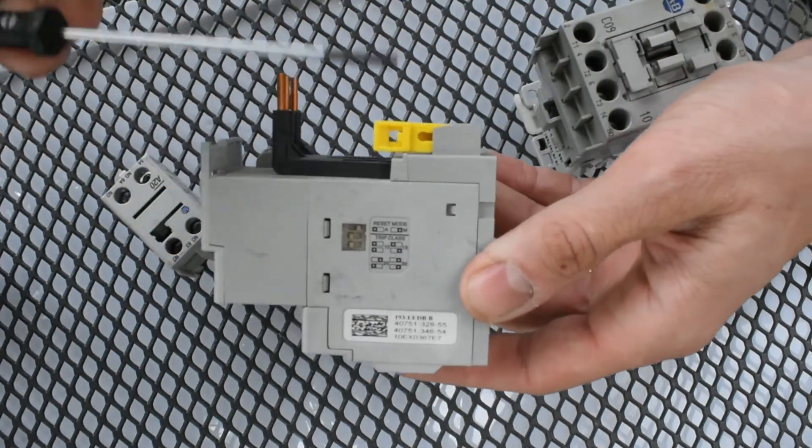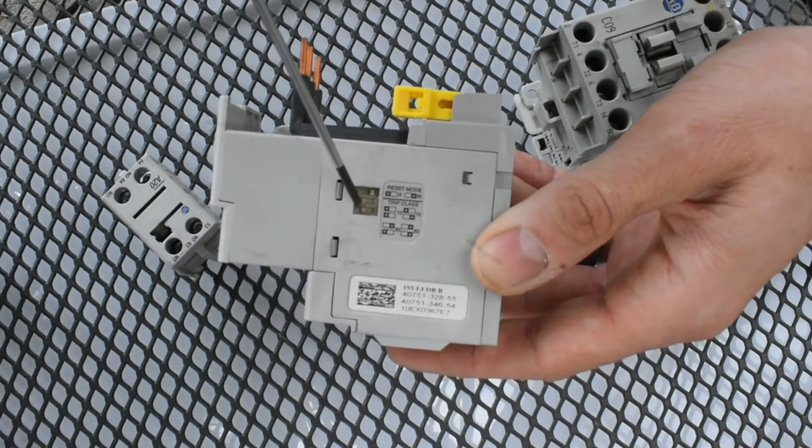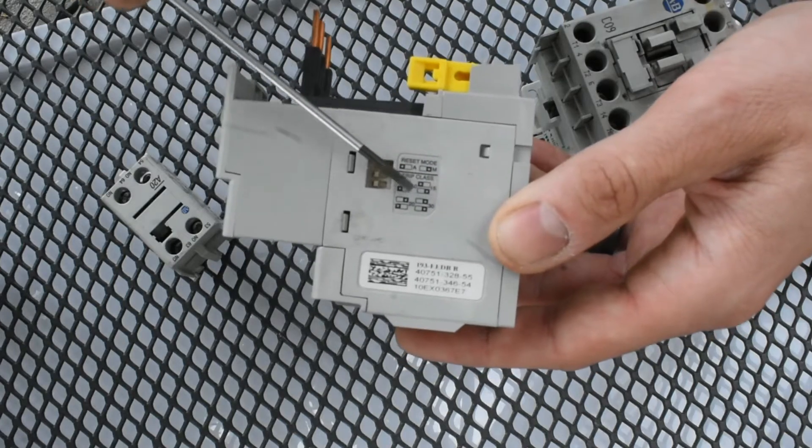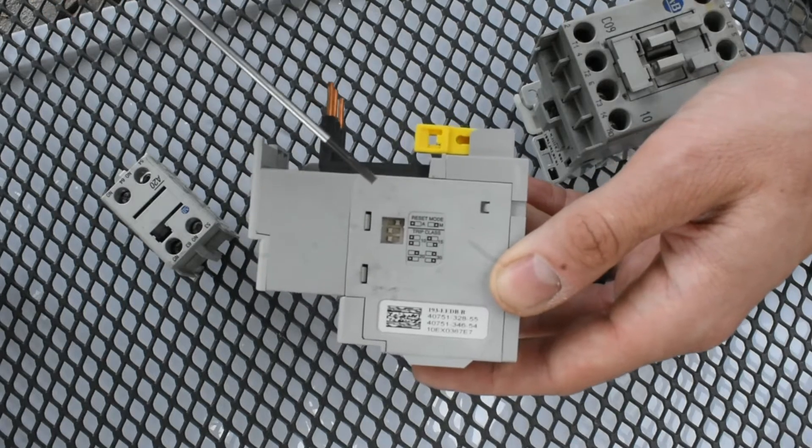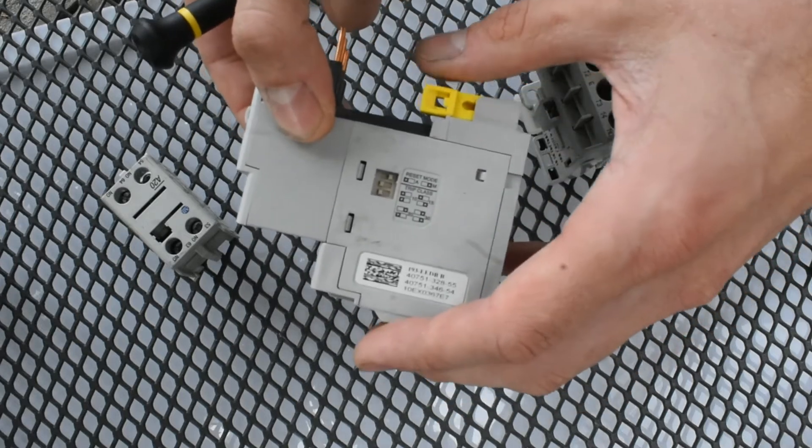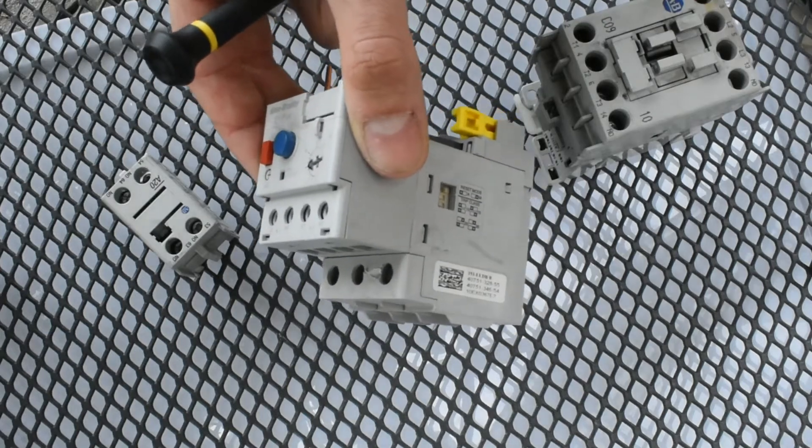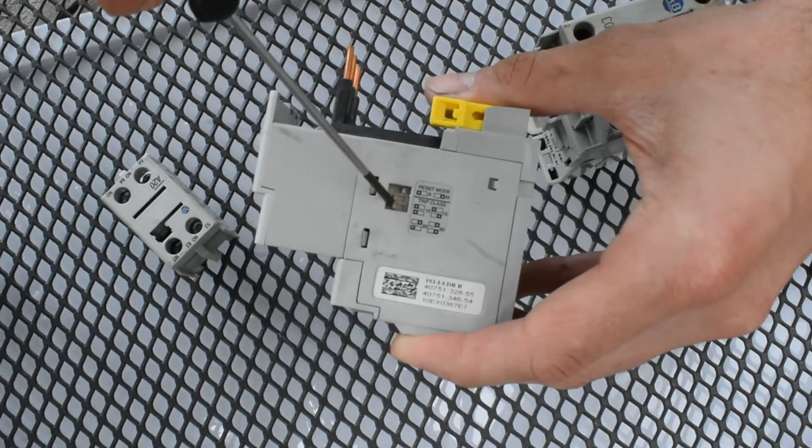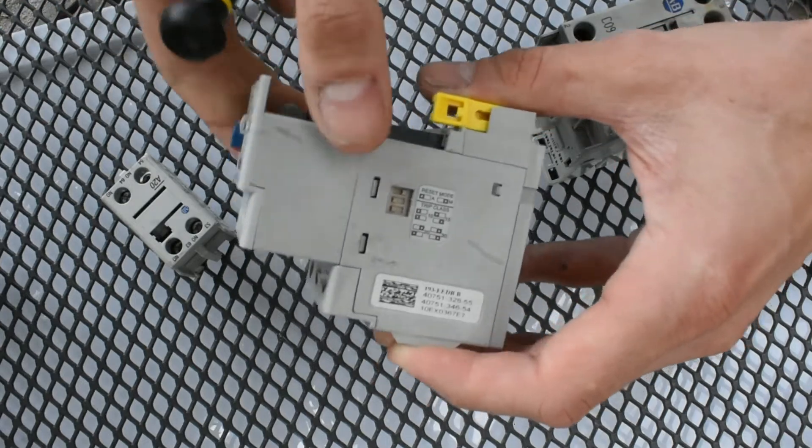Now, this one has a selectable motor trip class. You see a set of selector switches, and depending on the position that these selector switches are in, it has a trip class that's either 10, 15, 20, or 30. And that refers to the number of seconds that the motor, that this overload is going to be able to withstand a much higher current. So if we have a relatively slow startup for this motor, and it's going to take 30 seconds of high current, and that's okay at the beginning, in fact, it's expected, then I would want to set these selector switches into the position that allows the trip class of 30 for 30 seconds.